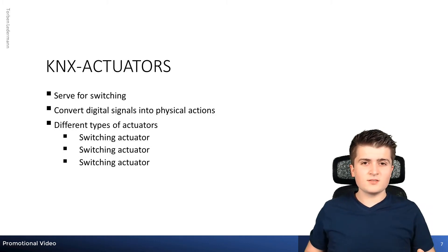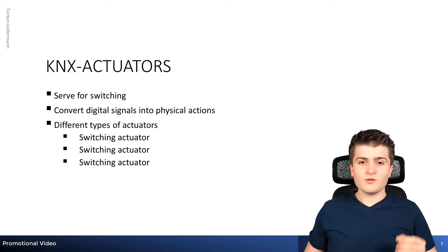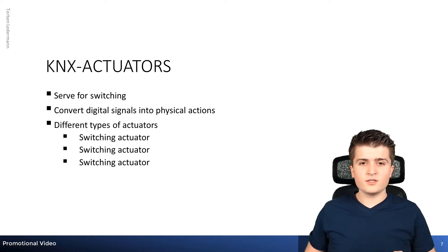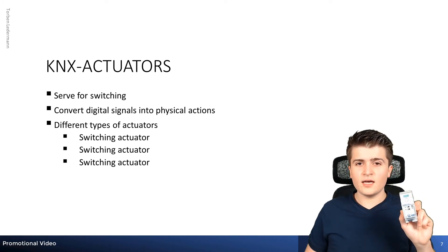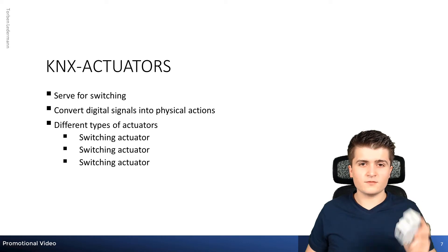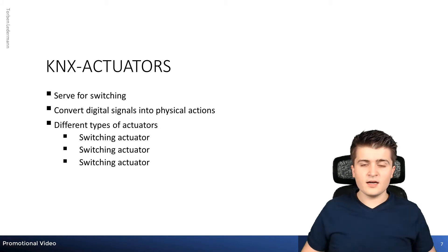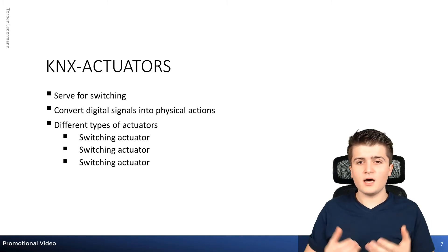Now that we know the sensors, we also need to know their counterpart: the actuators. With actuators we are able to convert digital KNX telegrams into physical actions. Depending on the action you want to perform there are different actuators — for example, a switching actuator to switch lights on and off, a dimming actuator to dim lights, and other actuators for specific applications like heating actuators and blind actuators.